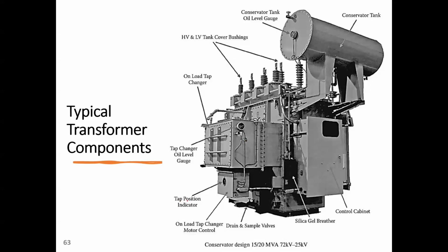Here also we have the tap position indicator. So here you have an indicator. You can see at which place your tap is right now to figure out the right position of your tap. Can you see here also, guys, the on-load tap changer motor controls. So the tap is not manual. It needs motor control in order to control the position of these taps. So this is also another drive system used to control the tap position.